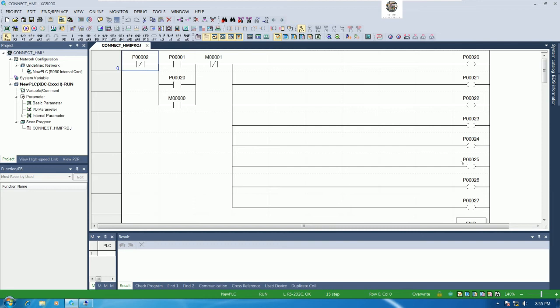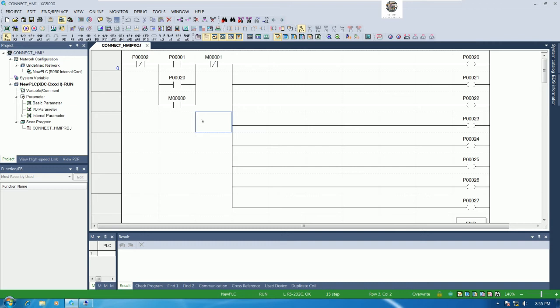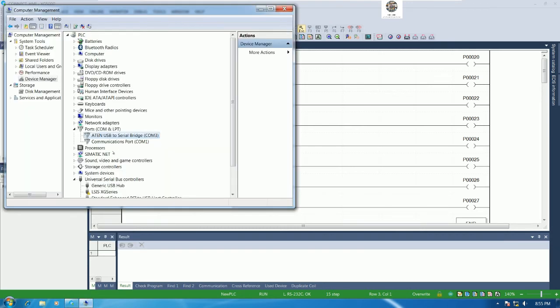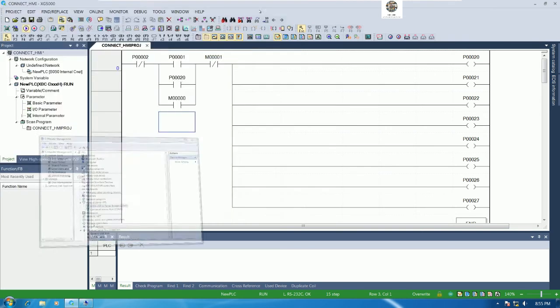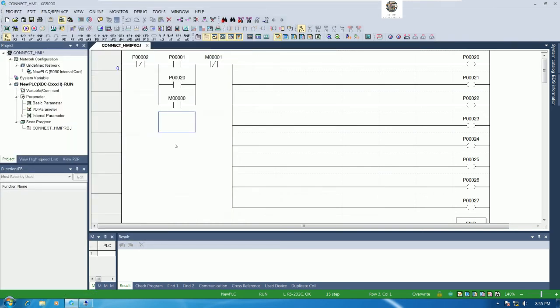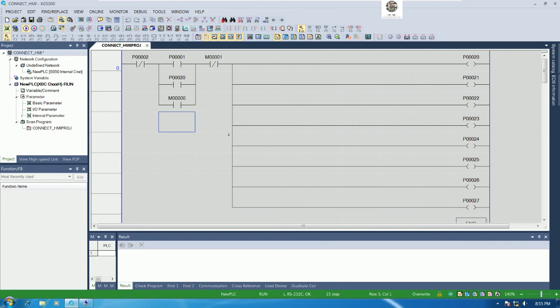Right now it already connected and uploading the program. Finish. And then we will got this project. So first we need to connect the USB converter and then update the driver to be matched with our hardware for COM port and then connect to RS232C cable, then connect to the PLC with our computer.